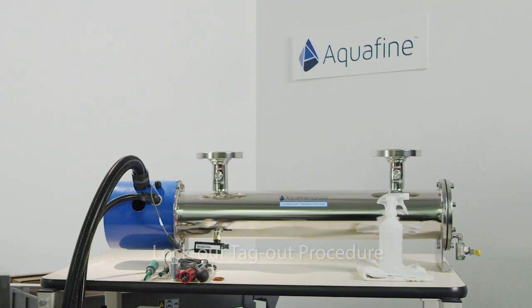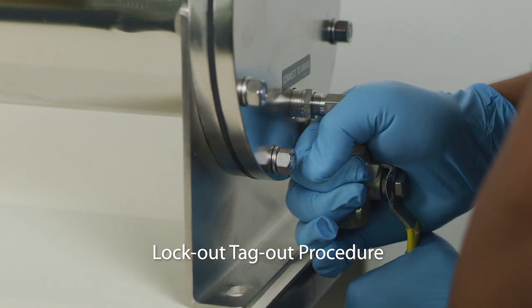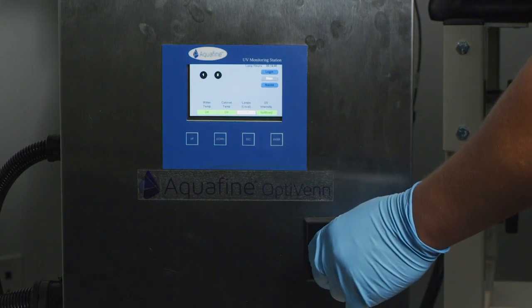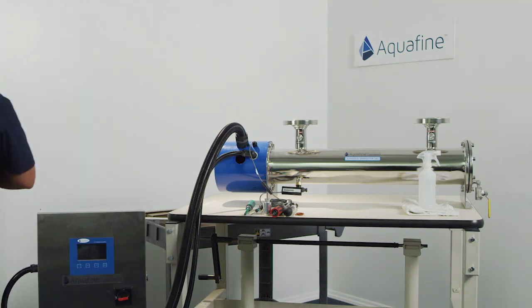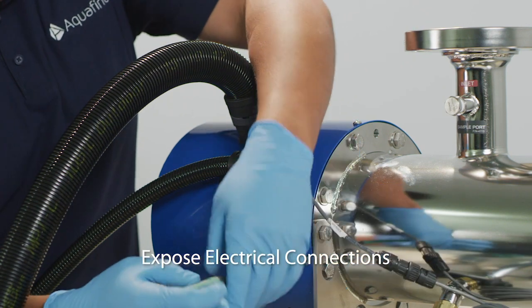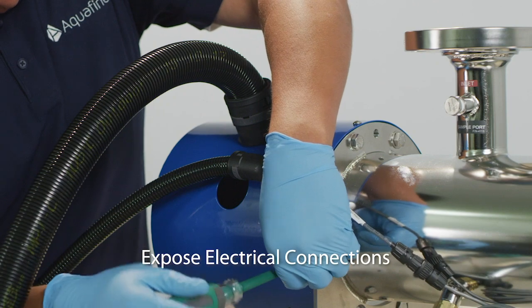Prior to performing any service on the unit, ensure that lockout-tagout procedures are followed. Water flow has been shut off and valves closed to prevent water flow. Make sure that the unit has been properly depressurized by opening the drain valve. Be sure to use non-powdered latex gloves before performing preventative maintenance.